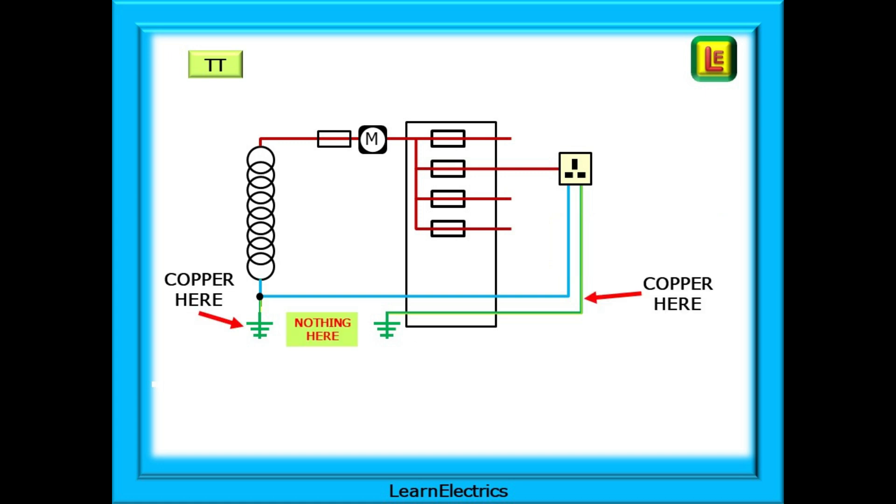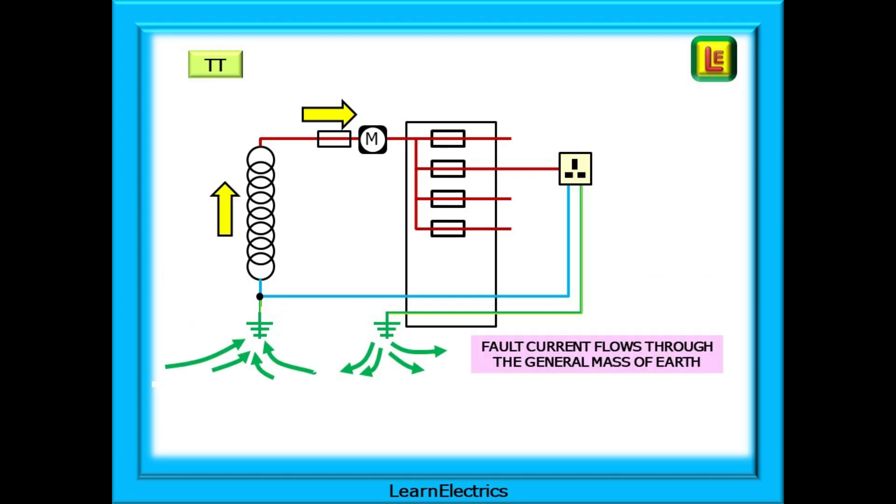Looking at the drawing for a TT system, it is very different to the other two systems. There is no metallic Earth connection between the supply transformer and the installation Earth. Having no metallic connection means that we are going to get a higher ZE reading. With no metallic connection, what happens to any fault current? It simply flows into the general mass of Earth. Because some electrons have flowed into the Earth at the installation Earth rod, there is now an opportunity for other electrons to flow into the Earth rod at the supply transformer. They will be energised, they will flow along the phase wire, through the fuses, and blow the fuses, making the installation safe, if you can get enough current to flow, that is.